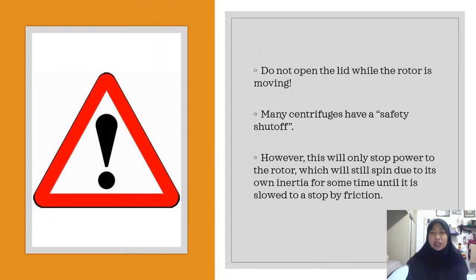This is what you should not do: you should not open the lid while the rotor is moving. Many centrifuges have a safety shut-off. However, this will only stop power to the rotor, which will still spin due to its own inertia for some time until it is slowed to a stop by friction.